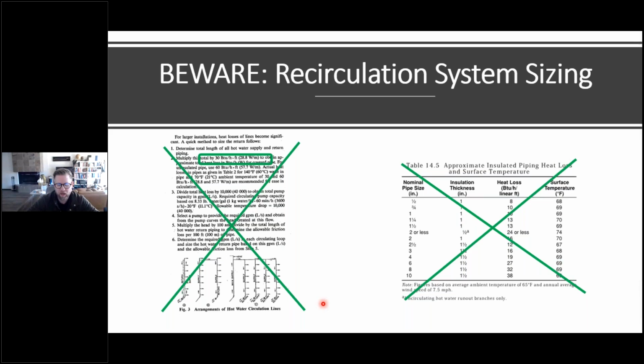This comes from ASPE's water heating design manual. This is actually good information. However, it's not expansive enough, because the assumed temperature for the system is 120 degrees Fahrenheit. Many of us as designers are starting to change our fluid temperatures, 140, 160, especially in regards to waterborne pathogens. So we can't use this one chart for all those instances. We need something that's a little bit more expanded. However, the information on this chart is good, and I would imagine that ASPE is in the process of updating this. Again, the latest information is in the ASPE Legionella Design Guide, which I would recommend getting yourselves a copy of if you have not already. So let's start with the base equations.